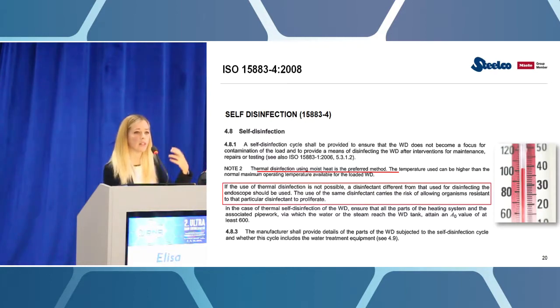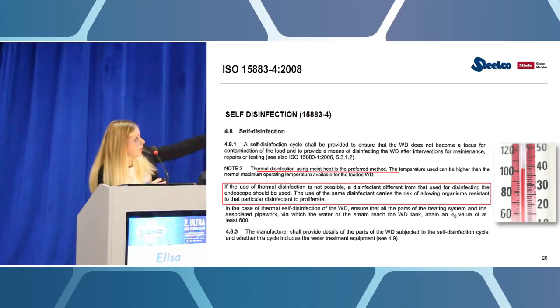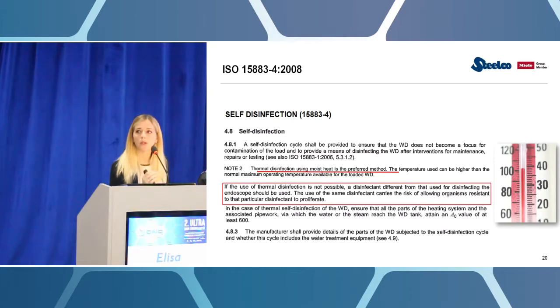So what shall we do? We need equipment with the possibility of either chemical or thermal self-disinfection. The standard specifies that thermal is the preferred method, because with chemical self-disinfection we'd need to change the chemical again. We can't use the same chemical as the normal cycle, since over time bacteria can develop resistance to that specific substance. That's why we'd need to change chemicals, and that's an added cost for you.